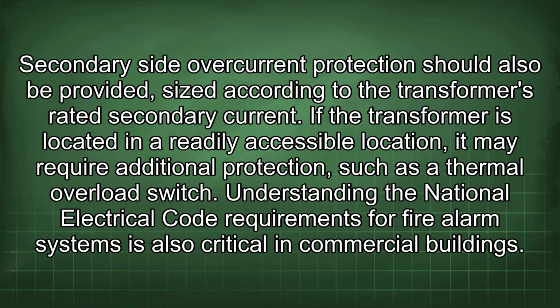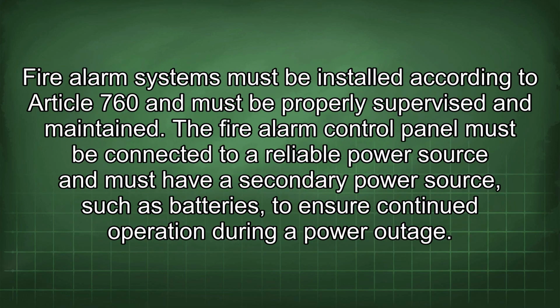Secondary side overcurrent protection should also be provided, sized according to the transformer's rated secondary current. If the transformer is located in a readily accessible location, it may require additional protection, such as a thermal overload switch. Understanding the National Electrical Code requirements for fire alarm systems is also critical in commercial buildings. Fire alarm systems must be installed according to Article 760 and must be properly supervised and maintained.